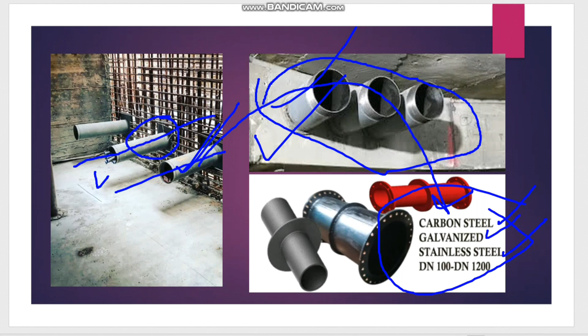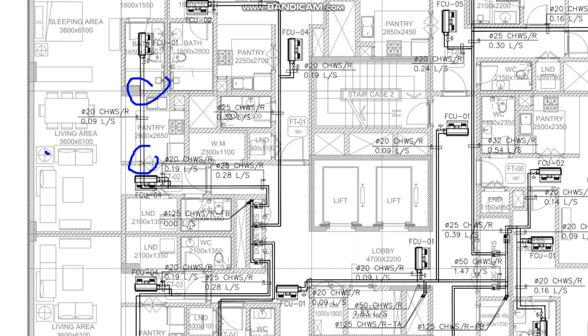This is not only for chilled water or district cooling systems - for any other service coming from outside and penetrating into the building, we must provide a puddle flange. But when it comes inside the building, for example where chilled water or district cooling pipes pass through different walls, we don't need puddle flanges. Instead we can provide a normal pipe sleeve. Let me show you that detail.